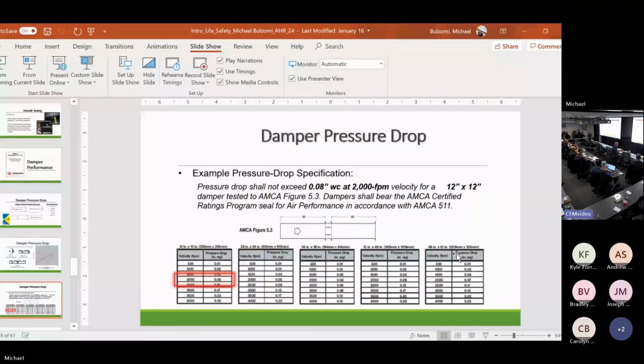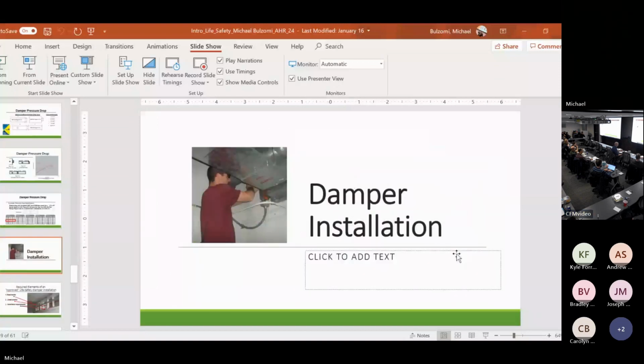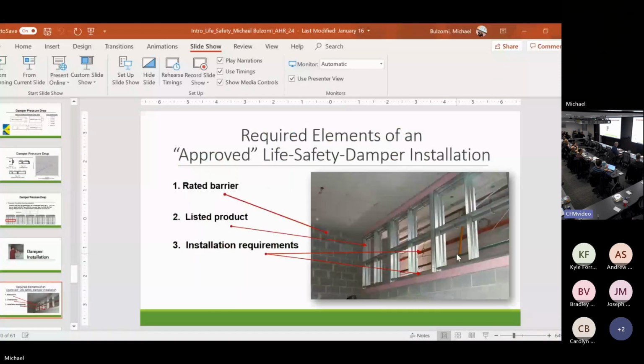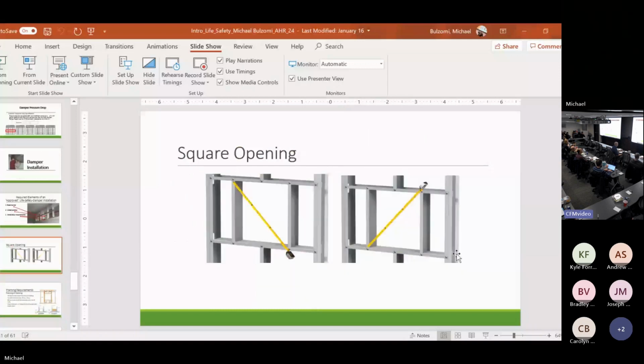Time here, that was a big one. Installation. I don't approve installation. So if you get a call from a contractor and he says, hey, I got a picture, send it to the manufacturer, I need this installation approved, I'm not an authority having jurisdiction. I can't approve anything. All I can do is point out deficiencies and point out things that look correct. If I physically am not there to inspect the damper, I don't make comments on pictures. Most pictures from contractors are usually the good side of the damper, never the bad side.